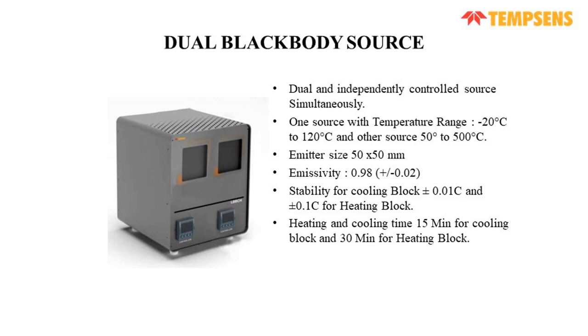The emitter size for this model is 50 by 50 separately, 50 by 50 for the heating one and 50 by 50 for the cooling one. Next, the emissivity is 0.98, and the stability for the cooling block is plus minus 0.01, and for the heating block is plus minus 0.1 degree centigrade. The heating and cooling time is 15 minutes for the cooling block and 30 minutes for the heating block. So this model offers -20 to 500 in a single body.